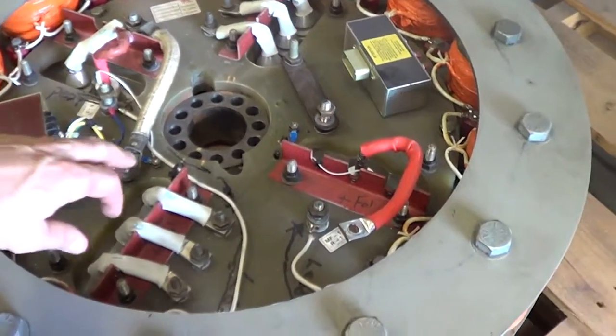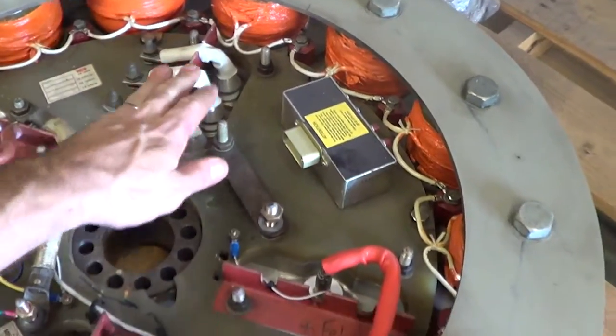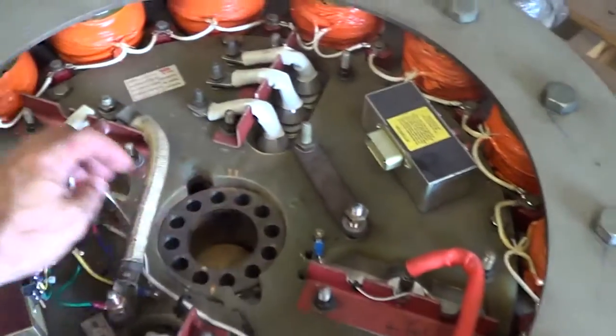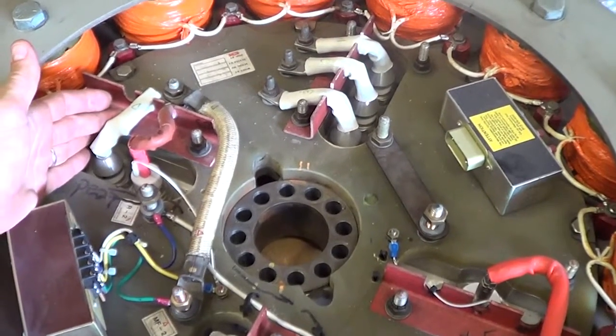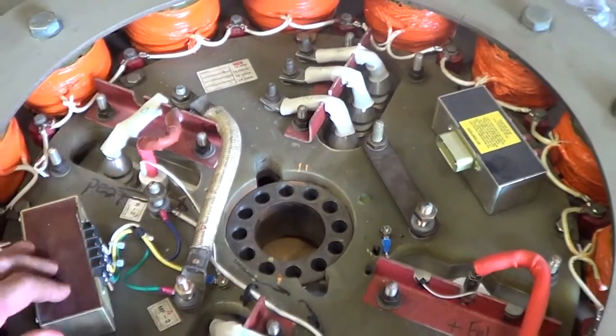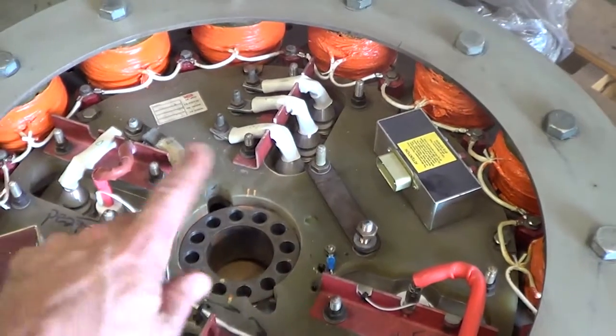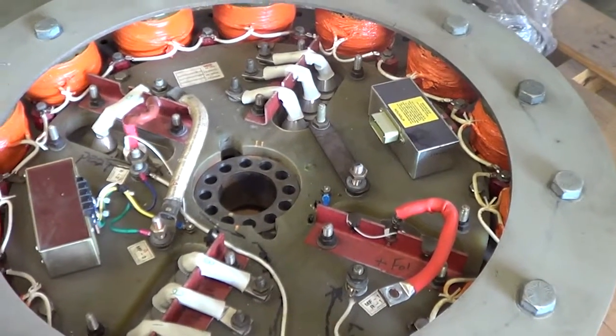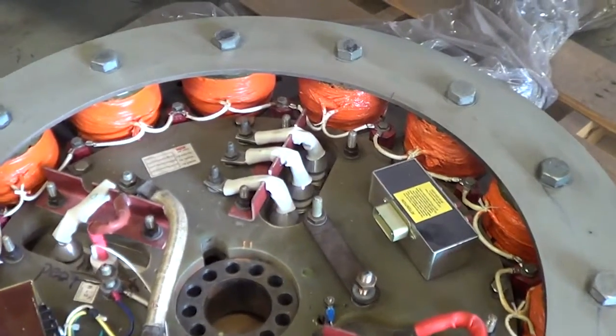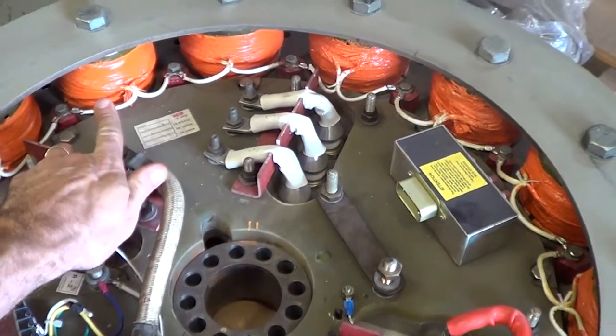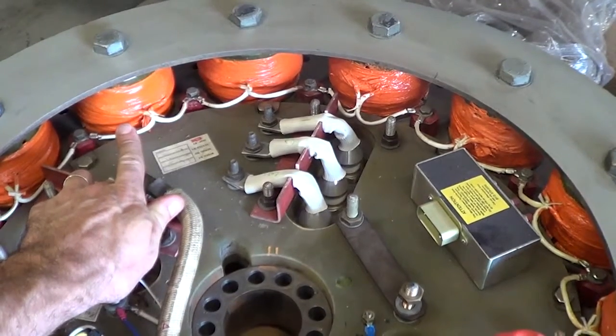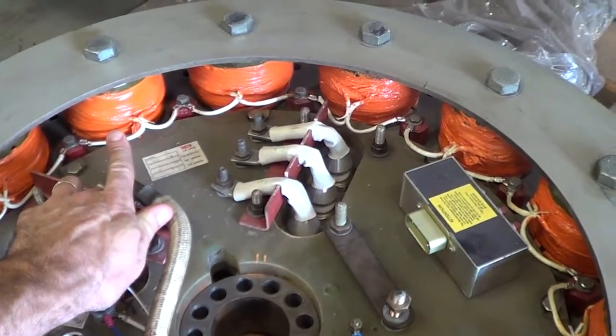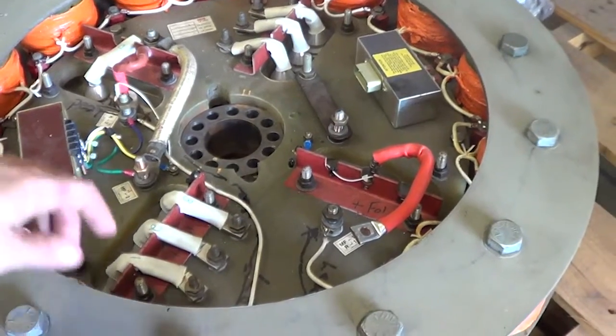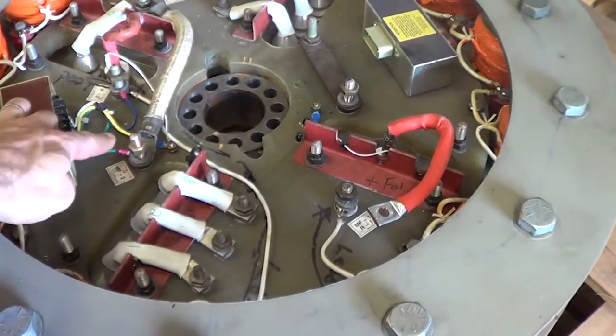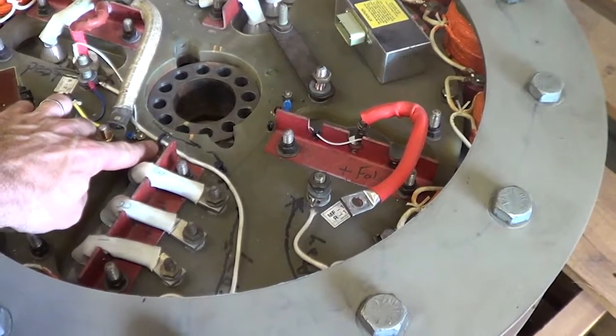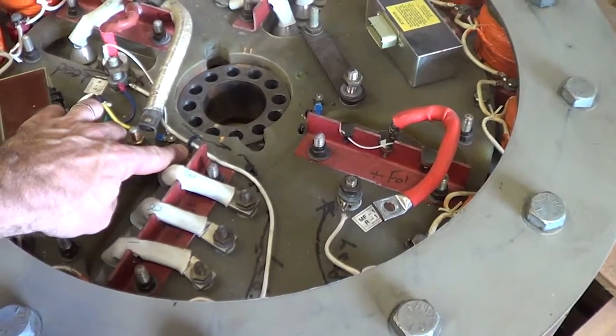For brushless synchronous motors, there is a wide range of diode wheel configurations. All diode wheels have 3 forward and 3 reverse diodes, as well as an SCR1 and SCR2, which is in parallel with an additional forward diode. Different control modules exist, but the main components can be tested using a simple Fluke multimeter. Some diode wheels include a set of field discharge resistors, which may be spool wound, as in this case, or standard heater elements. After testing the diode wheel, perform a tug test on all the connections and ensure a sufficient number of cable ties have been used to secure the cables to the wheel.